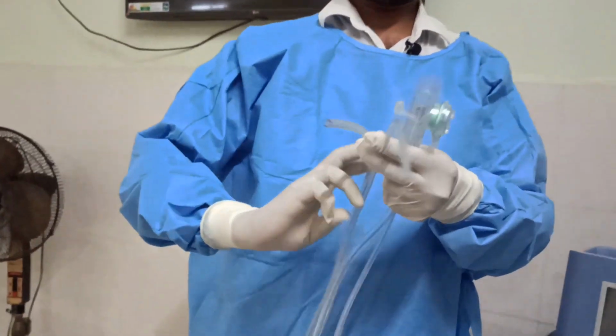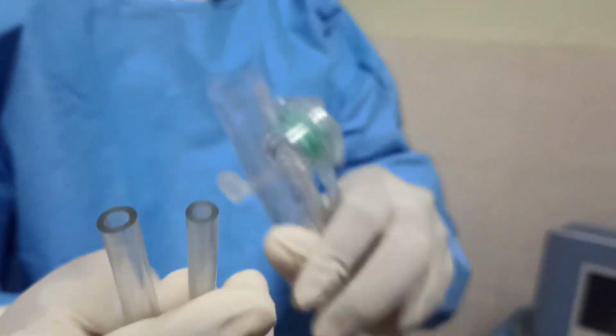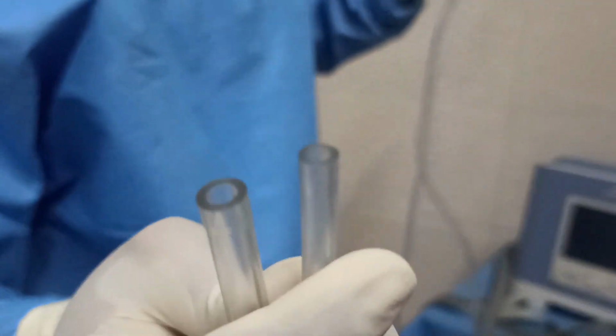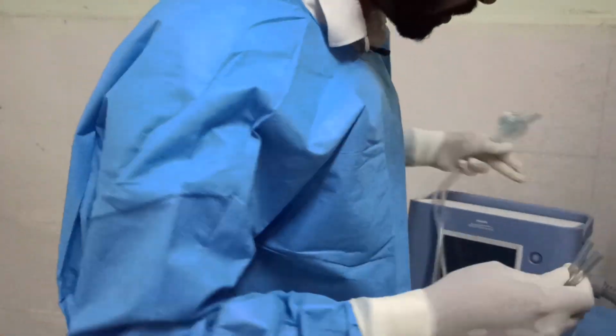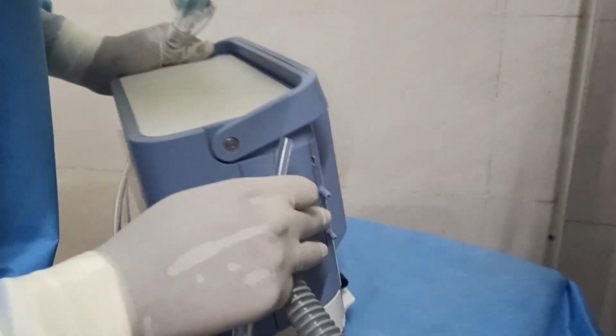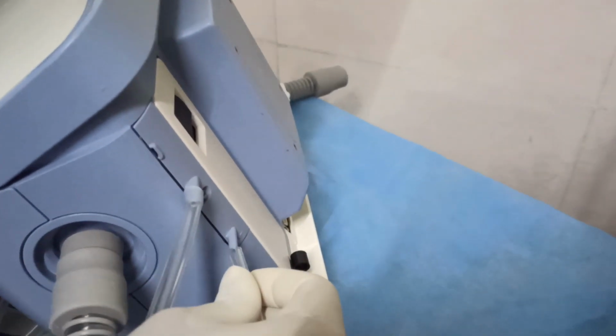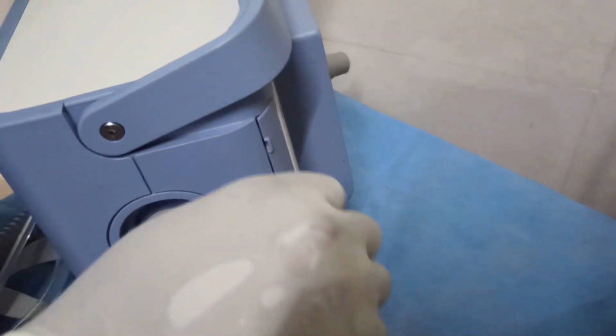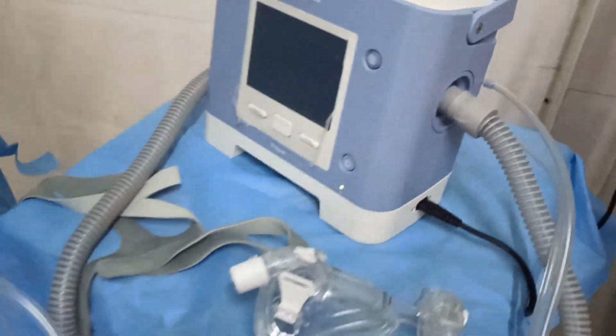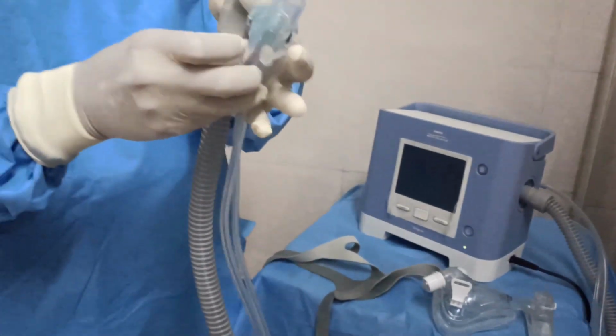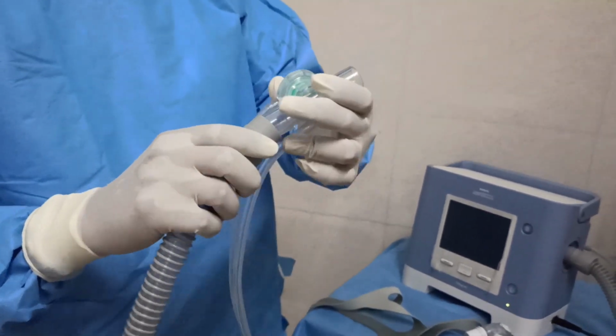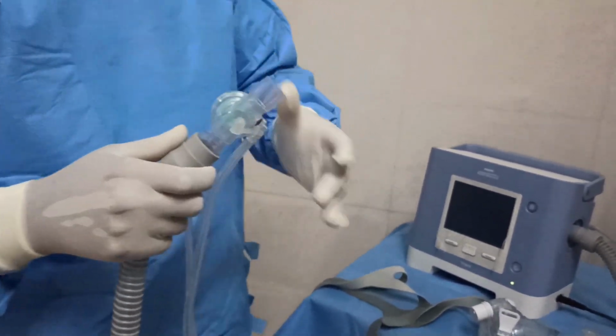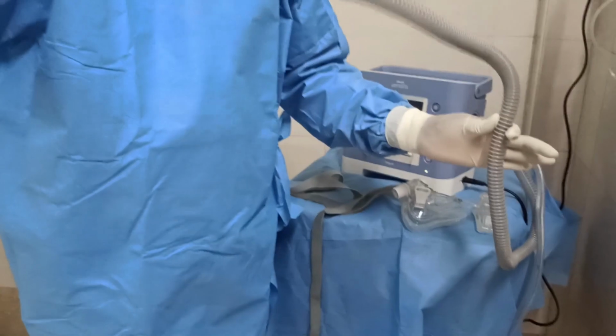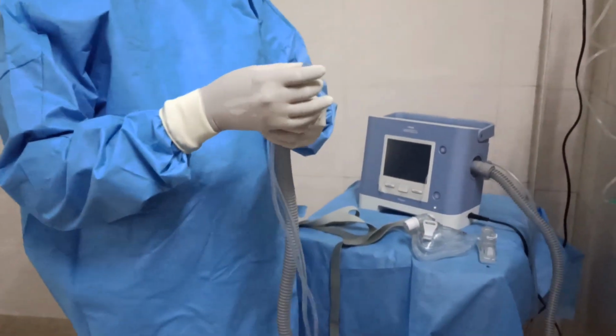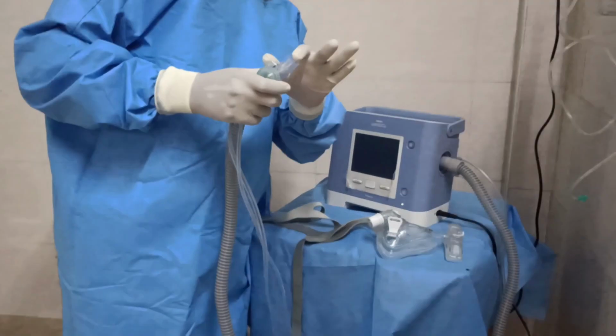These are actually of two sizes, a bigger one and a smaller one. So the diameter is bigger and smaller. Now you can see two ports here. Connect the bigger one with the bigger port and the smaller one with the smaller port. Now these tubes are connected to the ventilator. Now attach this valve to our tube. The air comes through this tube, and this side is connected to the ventilator.